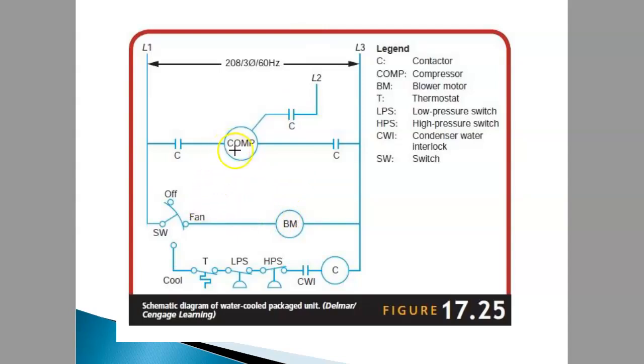Okay, how to make this compressor functioning? So to make this compressor functioning, we have to energize this relay. So when this relay is energized, what happened? All these three contactor relay normally open. Contactor relay will be changed from normally open to close position. Okay, but to make this one function, this CWI condenser water interlock has to be closed. So it has to sense there's water inside the system.